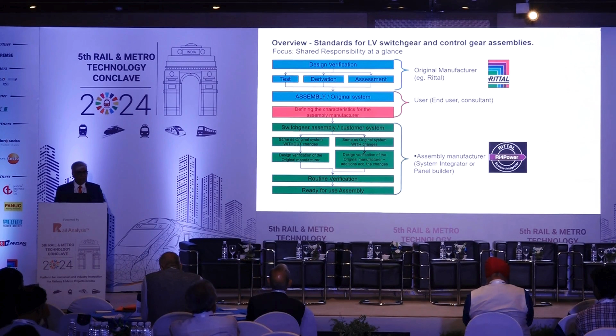Let's go through the chart of IEC 61439 and who stands where in this standard. There is the original manufacturer, for example Rittal, and there is an end customer, like Indian Railways maybe, who defines the characteristics needed, the incoming ratings and outgoing ratings. Then there's the assembly manufacturer who does the integration of the complete switchgear, bus bar, panel, and wiring. Rittal also has different authorized assembly manufacturers who take care of the integration as well.